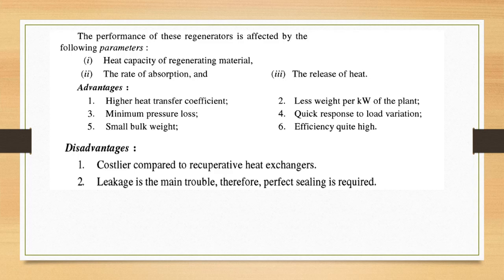The performance of a regenerator is affected by: the heat capacity of the regenerating material and the rate of absorption and release of heat. Advantages: higher heat transfer coefficient, less weight per kilowatt of plant, minimum pressure loss, quick response to load variation, small bulk weight, and high efficiency. Disadvantages: they are more costly compared to recuperative heat exchangers, and leakage is a main trouble, so perfect sealing is required.